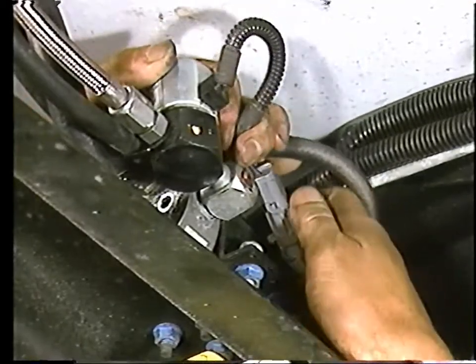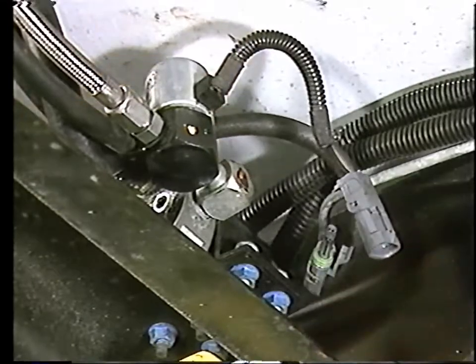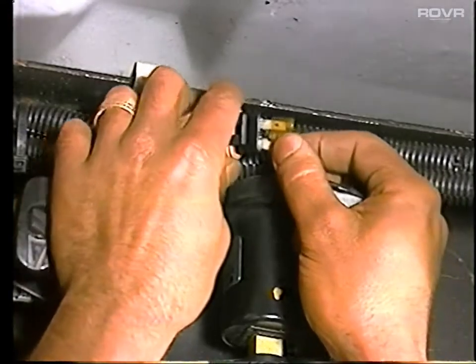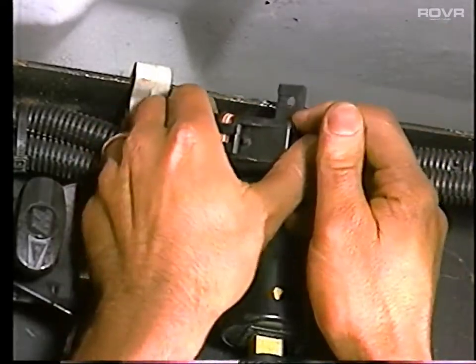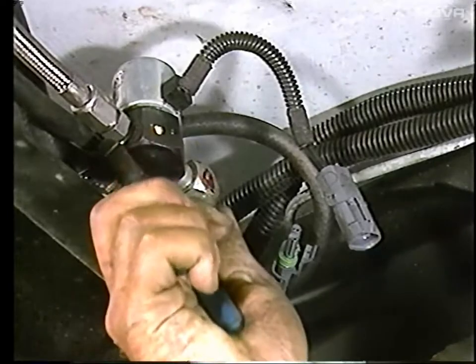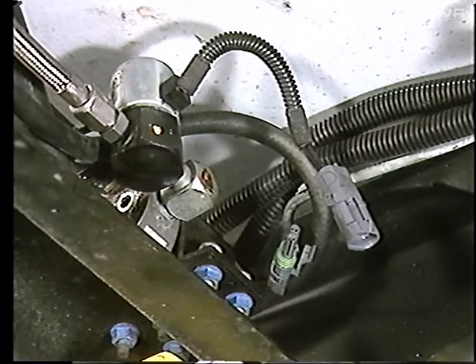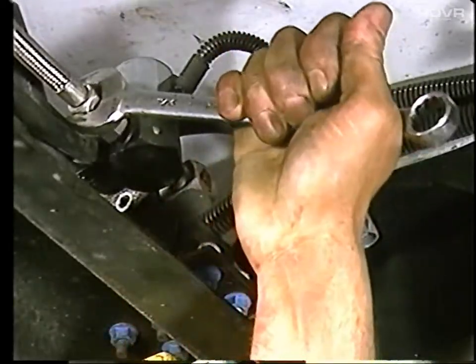But let's go one step further to be sure that you found the only electrical problem. Disconnect the inoperable solenoid. Replace the fuse. And continue to test the circuit to be sure there aren't any other electrical problems. Once you're certain that you have identified the failed component, replace it. Verify your fix. Put another fuse in if necessary. If it doesn't blow, you're okay, if there are no other electrical problems. Verify the repair by starting the truck's engine.